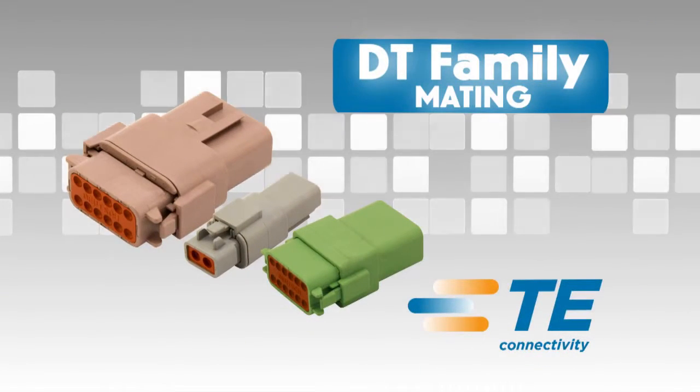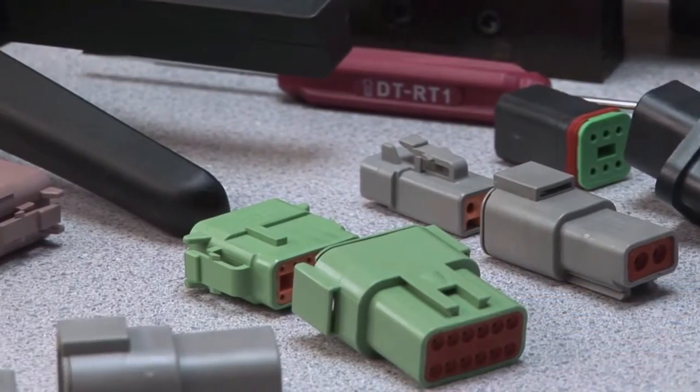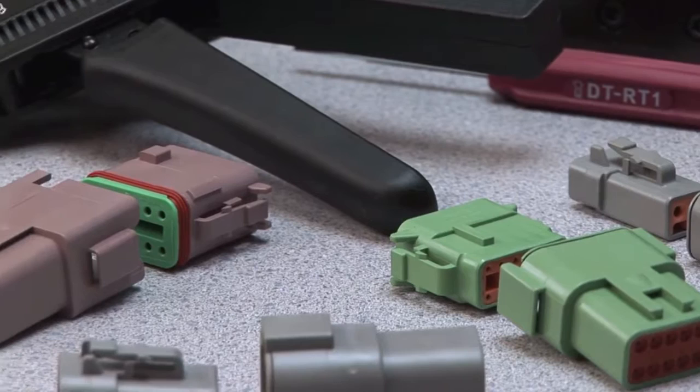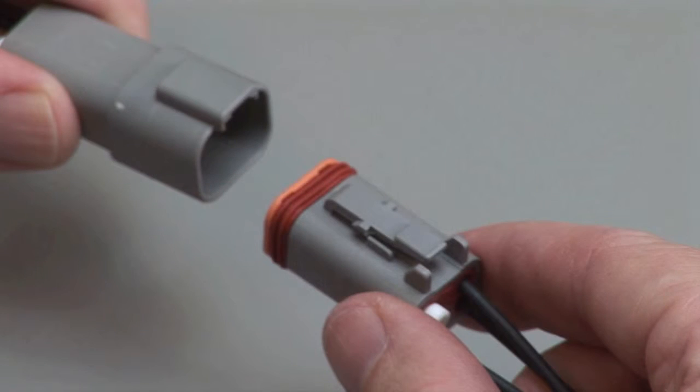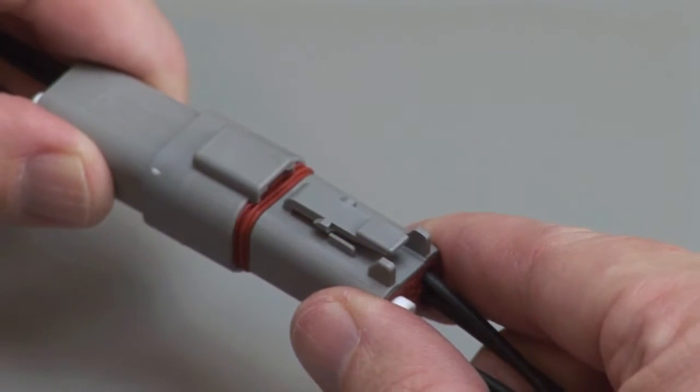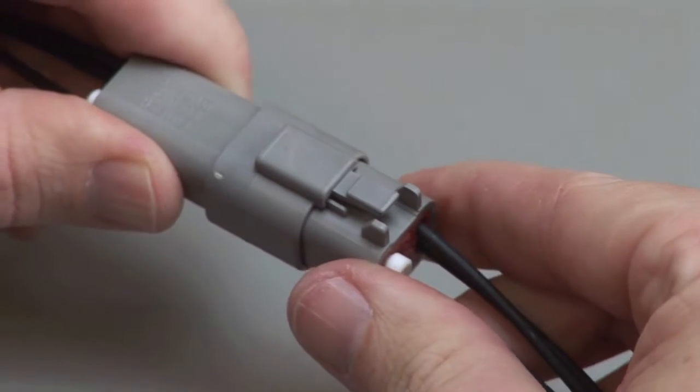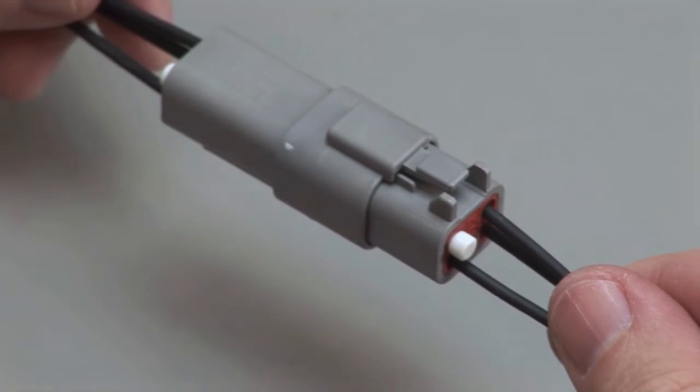DT Mating. All DT connectors are designed to be mated and unmated by hand. When mating a DT series, grasp the connector by the connector body and line up the exterior locking latch. Push the plug and receptacle together until you hear a click and the exterior locking latch is seated in place.